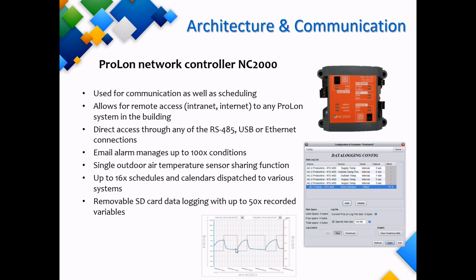Another feature in this device are the email alerts. These alerts can be set up to monitor any point on the system, whether it be temperature, pressure, an output, a status, and so on. Anything that can be read on our system. We can send each alert to up to 3 separate email addresses, and it can monitor up to 100 alert conditions.